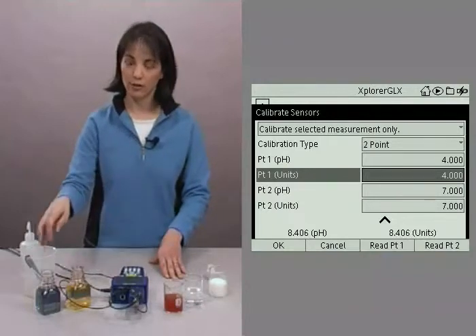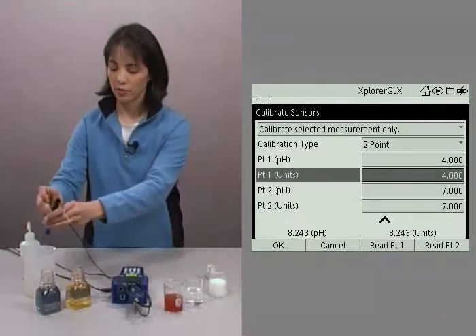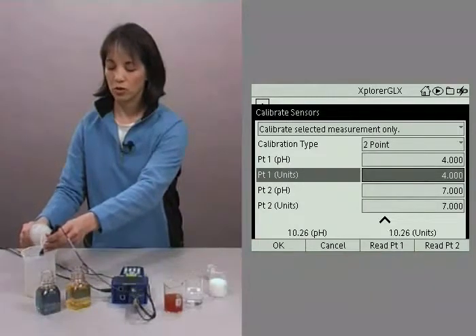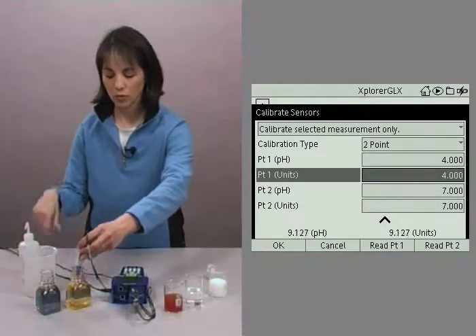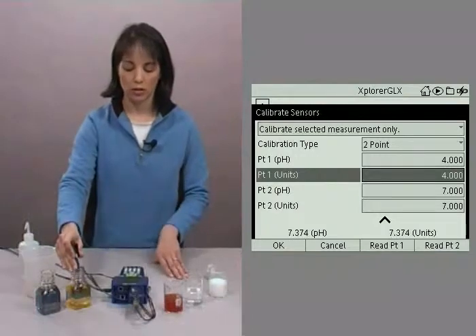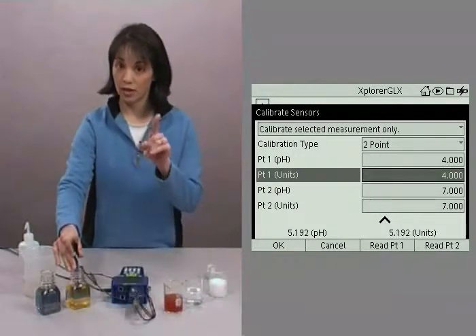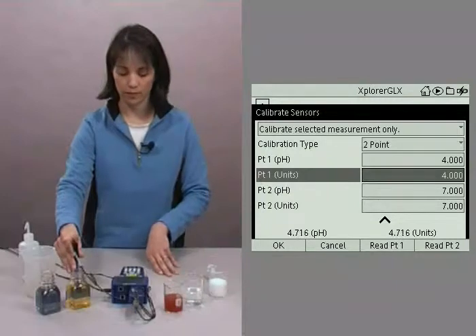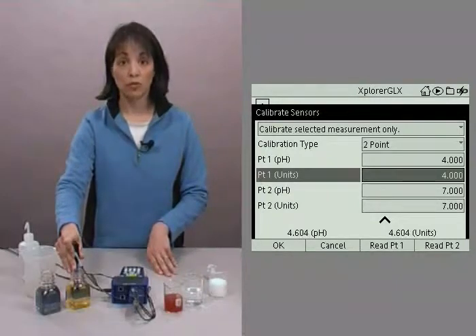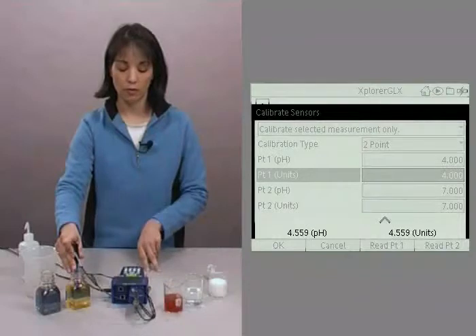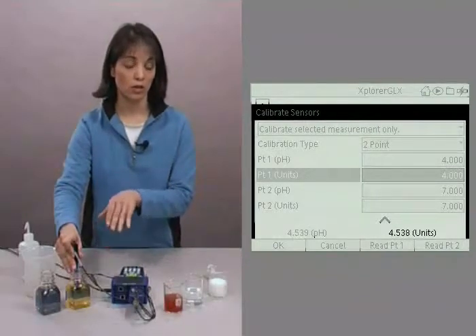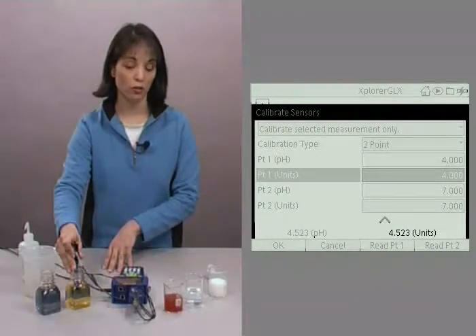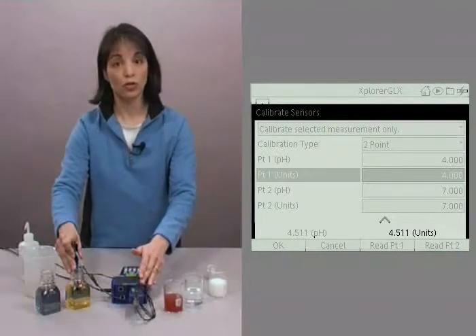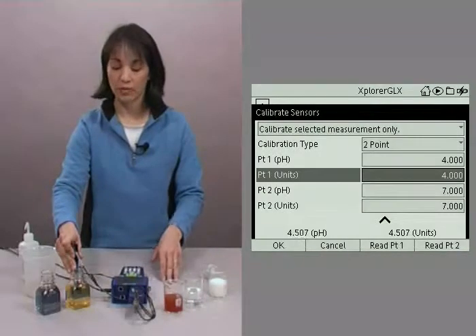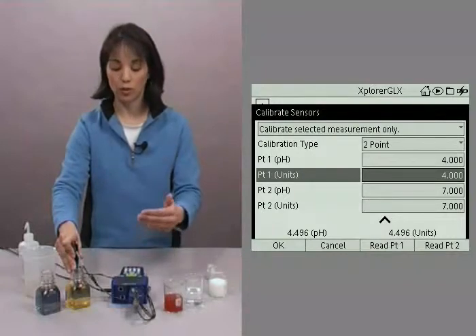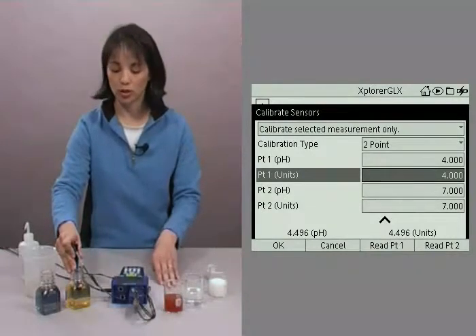Okay, now let me rinse it off, and let's put it into our buffer solution. It's actually quite easy, and it's not that value 4 that you see in there currently. Take a look near the bottom of the screen. There are 2 live readings there. The one on the right, labeled units, is the raw value that the Xplorer GLX sees from the sensor. That is the value that we want to put in that second field, also labeled units.